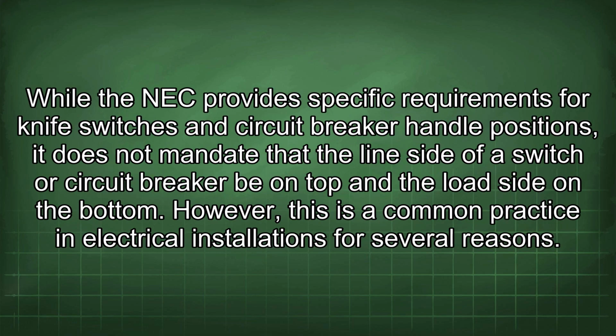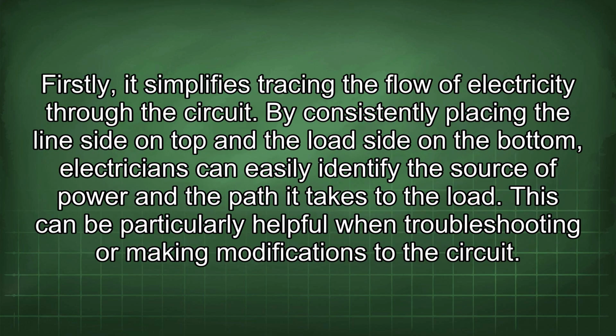While the NEC provides specific requirements for knife switches and circuit breaker handle positions, it does not mandate that the line side of a switch or a circuit breaker be on top and the load side on the bottom. However, this is a common practice in electrical installations for several reasons. Firstly, it simplifies tracing the flow of electricity through the circuit. By consistently placing the line side on top and the load side in the bottom, electricians can easily identify the source of power and the path it takes to the load. This can be particularly helpful when troubleshooting or making modifications to the circuit.